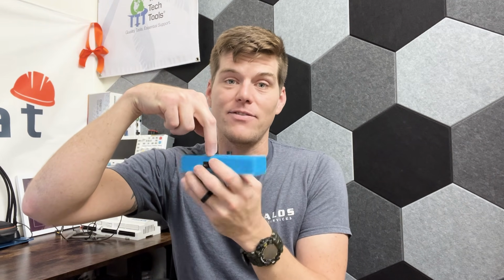The second caveat, some expansion valves, especially gear-driven expansion valves that go up to 2,000 pulses on indoor units, very famous EEVs in Daikin indoor units, can be overdriven open because it's a gear-driven type where a spindle sits inside of a device that when you drive it too high or too open, it'll actually disconnect that spindle from the gears. So what's the safest way to drive a valve? Well, knowing the range of that valve from 0 to 2,000 or 0 to 480 pulses is extremely important, but also understanding that the safest position to drive it to is closed or 0 pulses altogether on that piece of equipment.